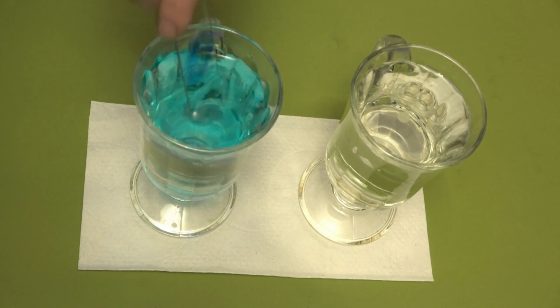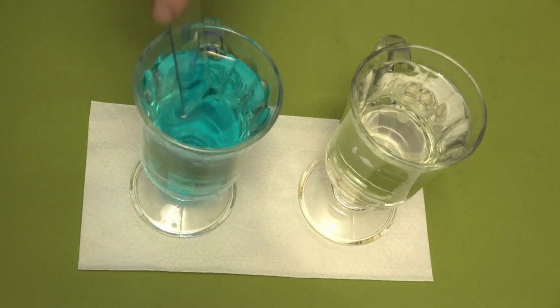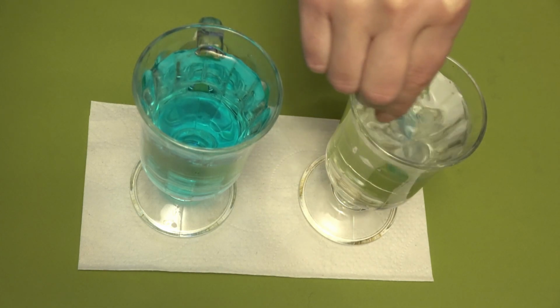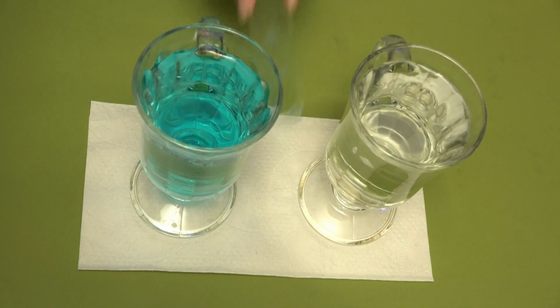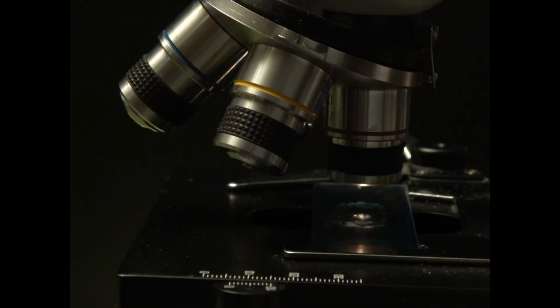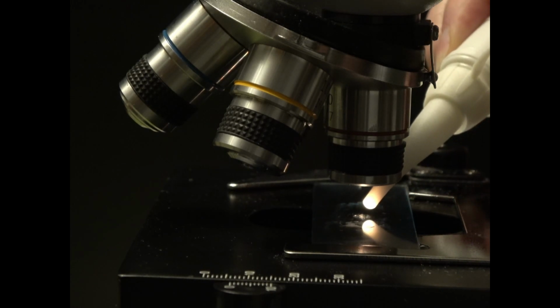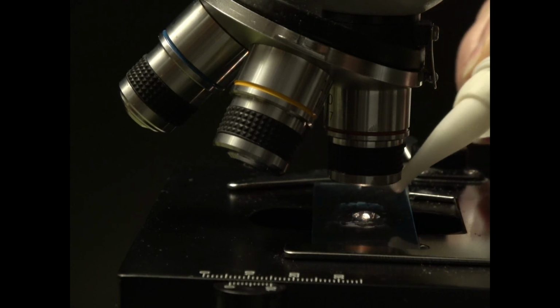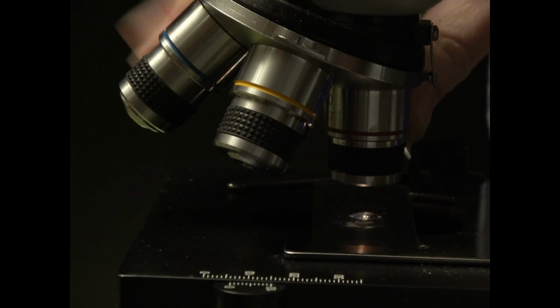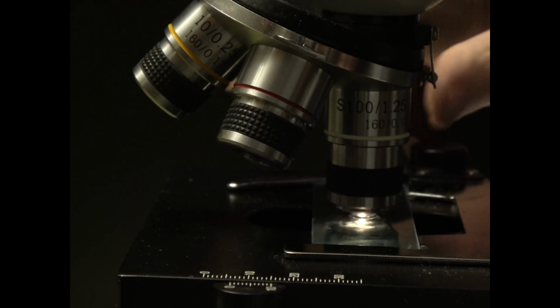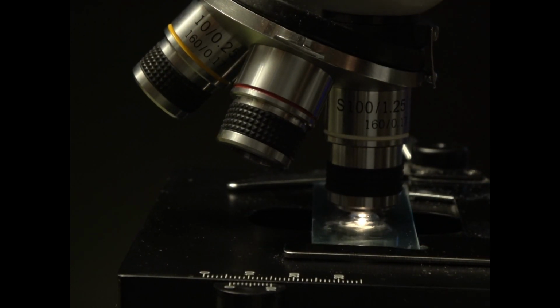These lenses are also marked with oil. This means it needs to be used with special immersion oil. You need to drop the oil directly onto the sample and immerse the lens in it. This way, we can avoid light refraction and distortion, similar to what we see when we put a pencil in a glass of water. An immersion lens is a good thing.